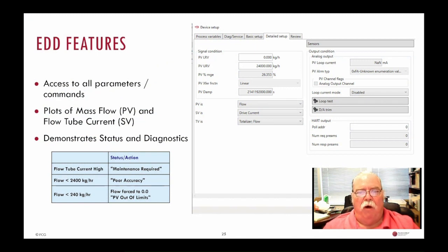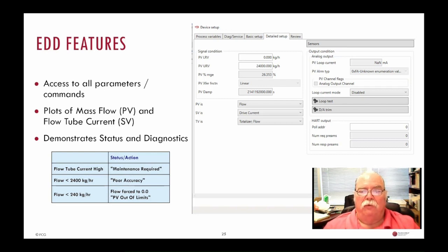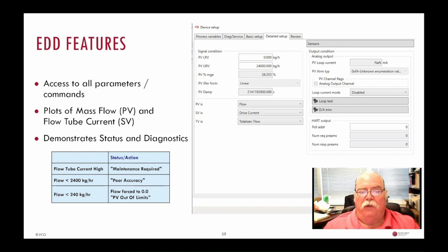Together, the EDD and FDI device package meet the minimum requirements necessary to register a device package. That means you have access to all parameters and commands associated with the flow device, representations of flow rates with engineering units, and plots of mass flow — the primary variable — and flow tube current — the secondary variable. It also demonstrates use of status indicators, such as maintenance required if the flow tube is becoming plugged. Most flow meters have a 10-to-1 turndown, so once below 10% of full range there's a poor accuracy status bit as well.